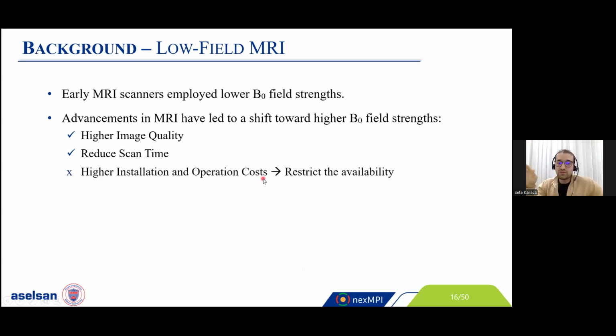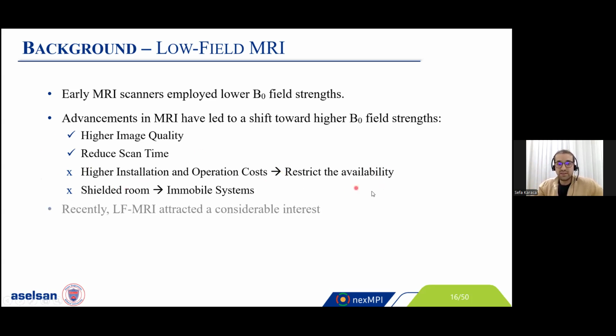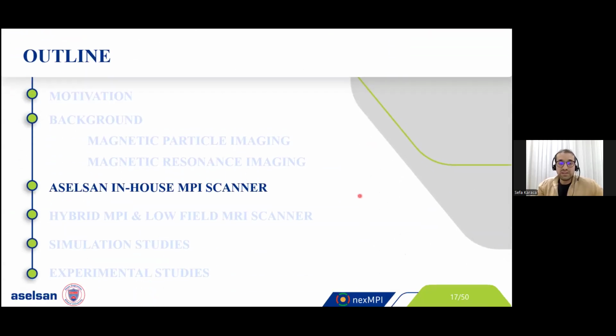But the problem with going to higher B0 field strength is that it also increases our installation and operational costs. There's one number in my mind: we need $1 million per Tesla. So in conventional MRI scanners, generally 1.5 Tesla scanners, the cost is $1.5 million. So it restricts the availability of MRI scanners. The other problem is they require a shielded room, so the systems become immobile. In order to reduce this disadvantage, recently low-field MRI attracted considerable interest, and the main purpose is to make MRI more accessible, even portable, while providing acceptable image quality for diagnosis.